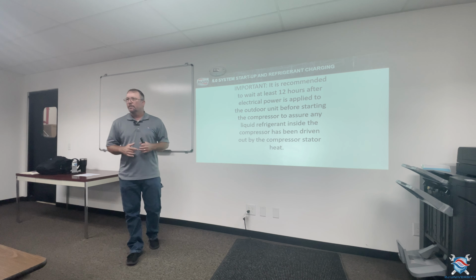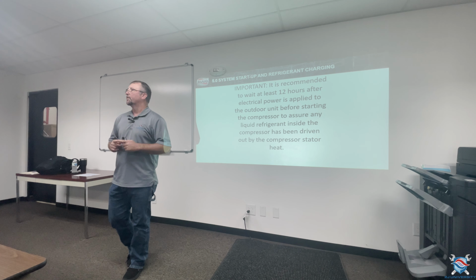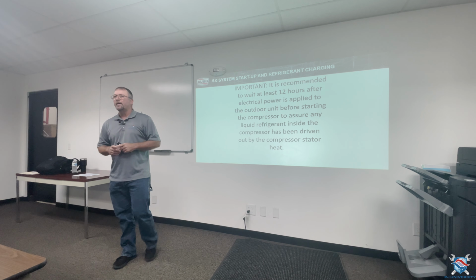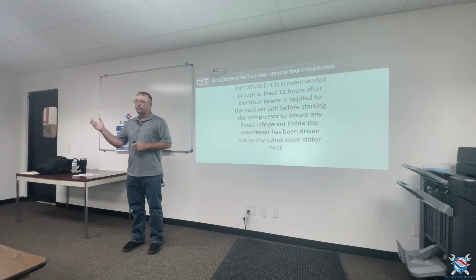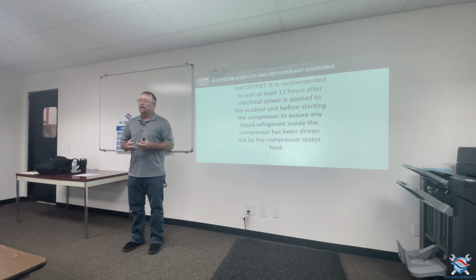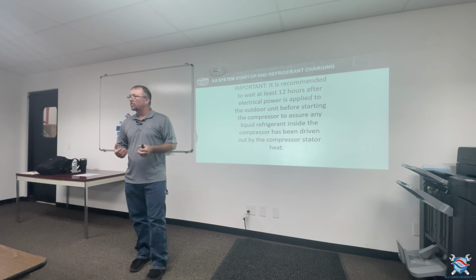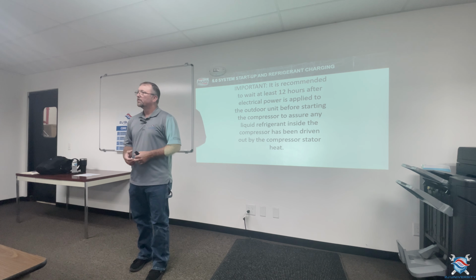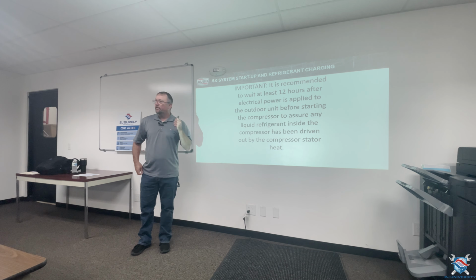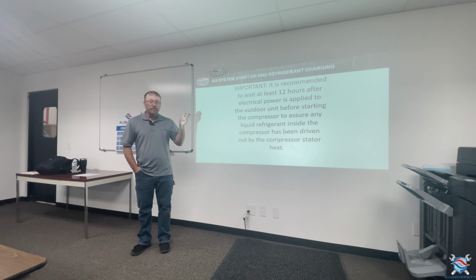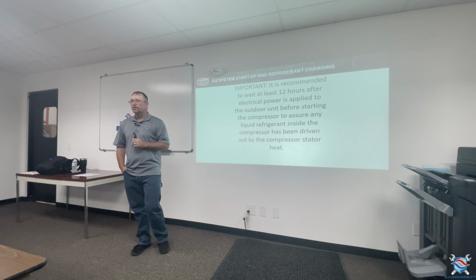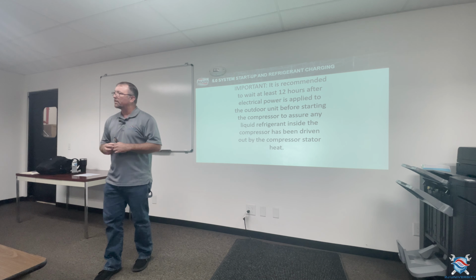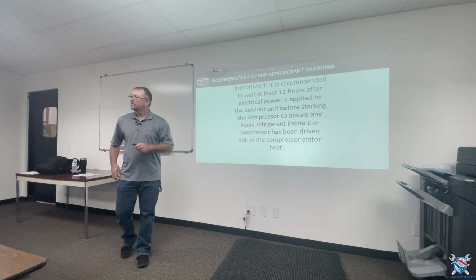My recommendation to you is get high voltage to the outdoor unit as early in the day as you possibly can, so when you're ready to walk off that job at 4:30, 5 o'clock in the afternoon, everything's good to go, and you can power that unit and probably have pretty good confidence that it's going to start and run. Reason being is because inverter compressors don't have the starting torque as a PSC style compressor. So you always want to make sure. You will get funny codes. You'll get inverter fault codes if there is liquid refrigerant trapped in that compressor and it will not allow it to start. So just something I wanted to point out.